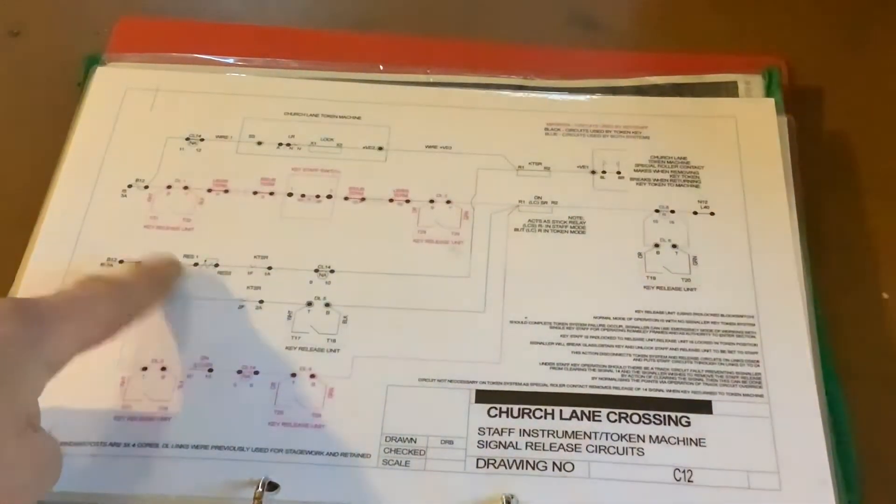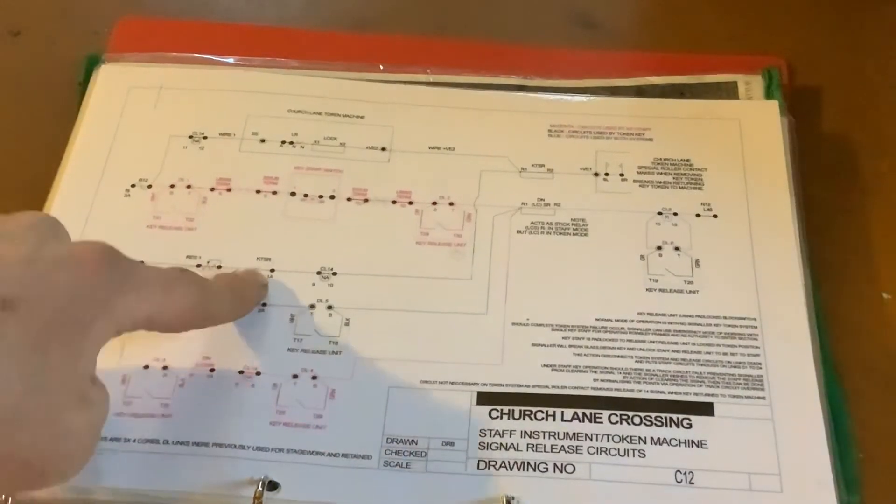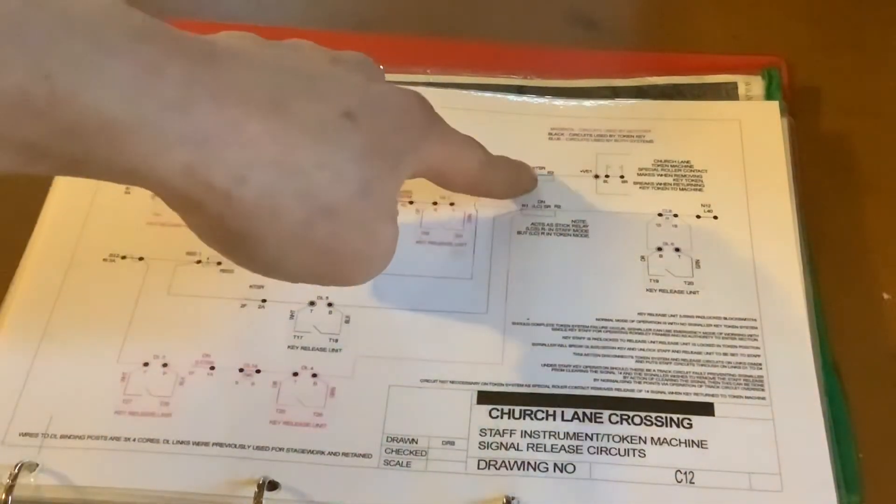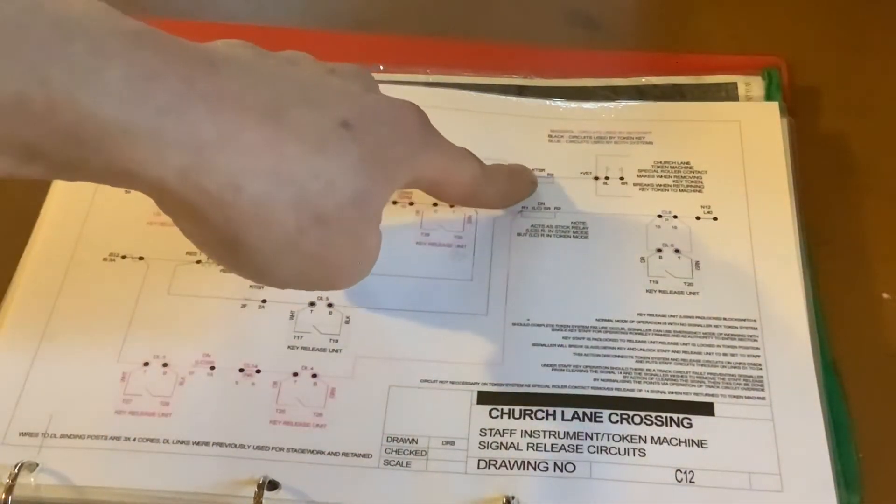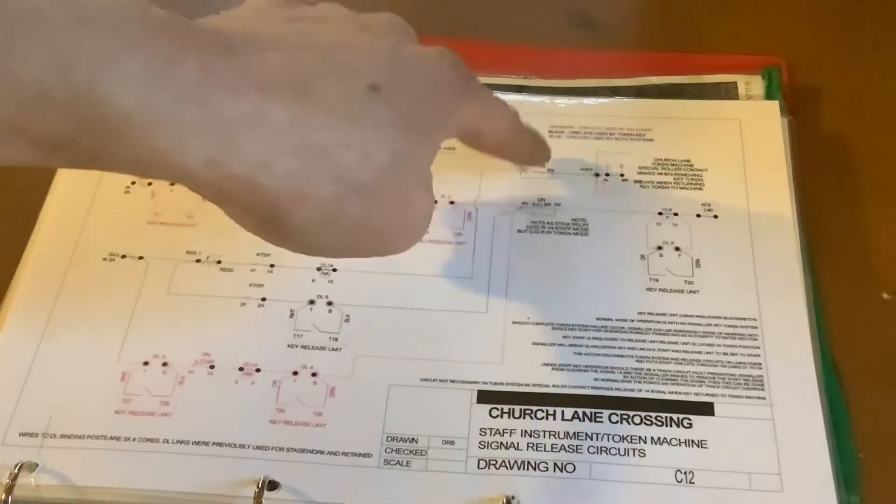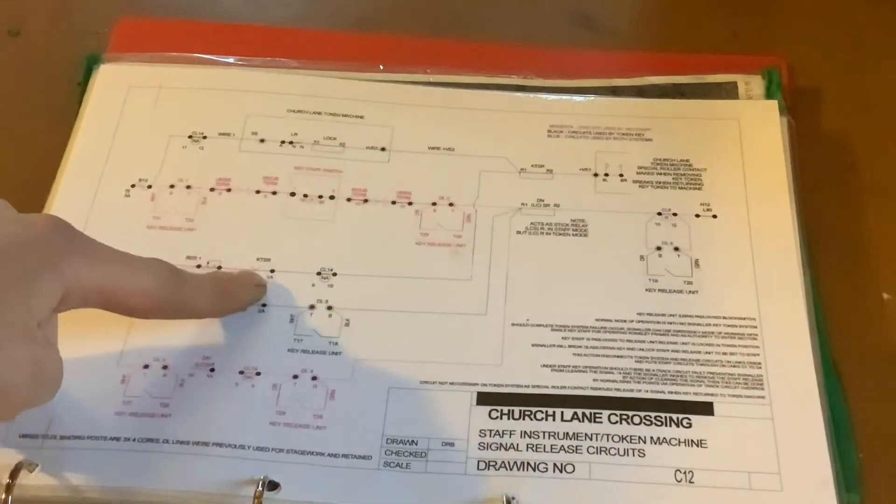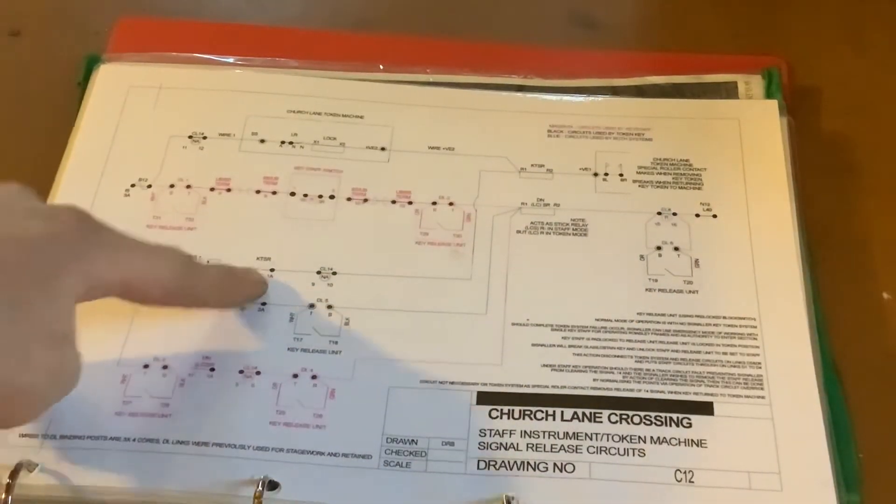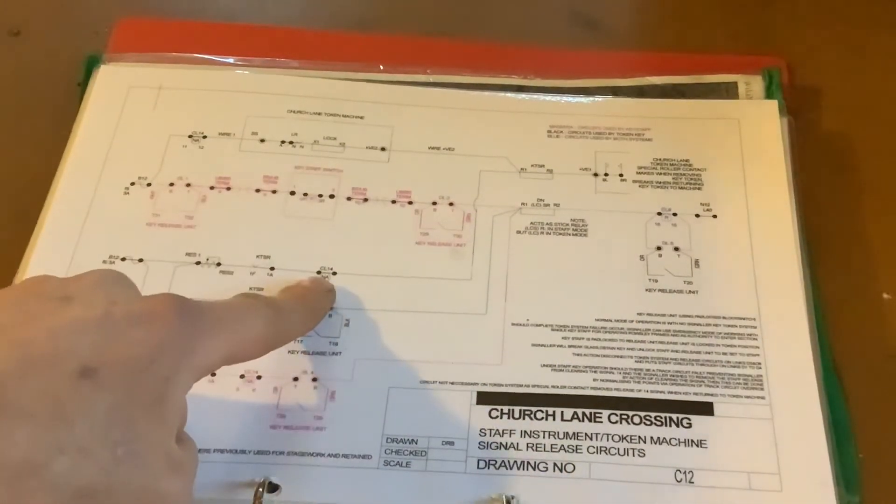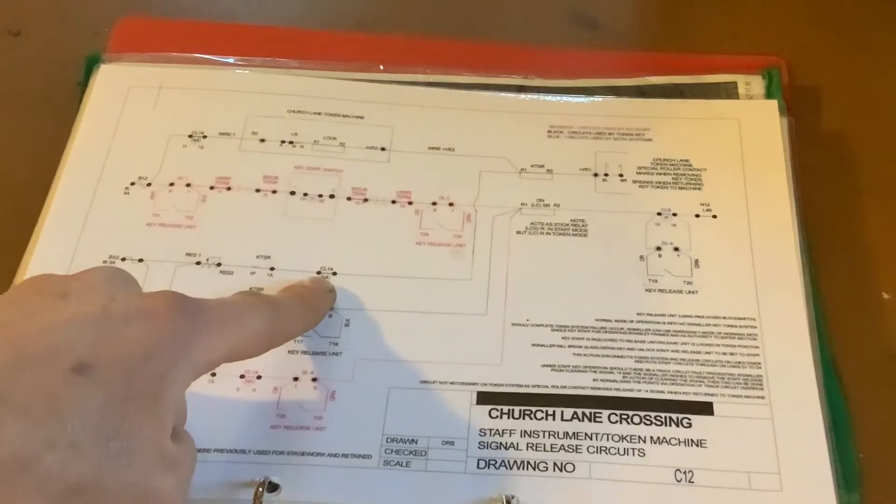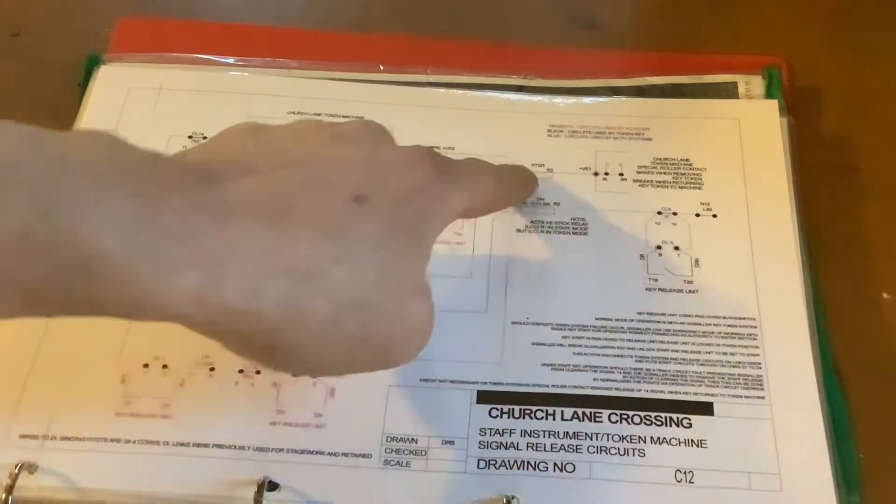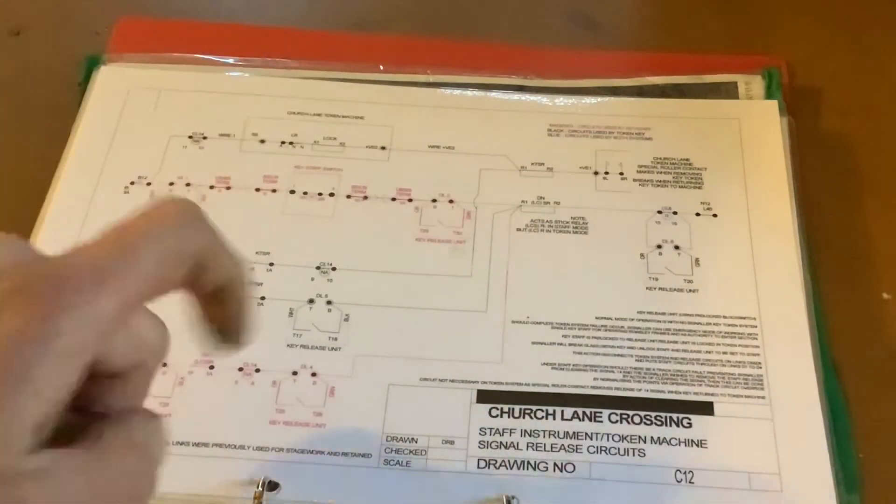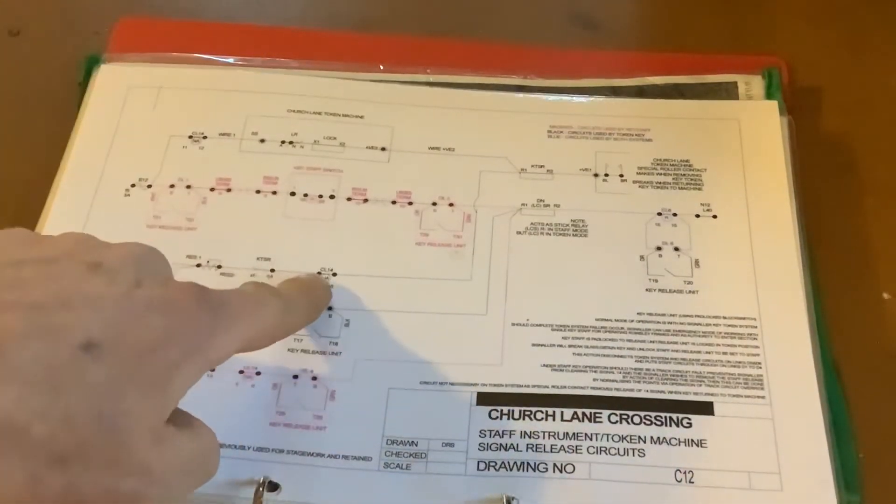And again, if we go down here, we notice then that with our key token stick relay up, this is our key token stick relay, it's memorizing again through this path. As long as we haven't pulled our starting signal off, that will stay up.